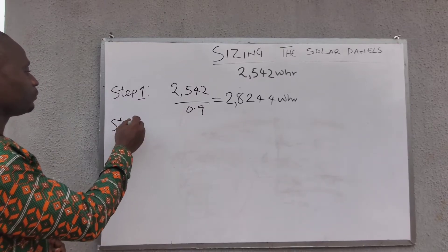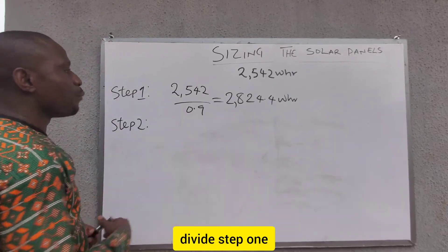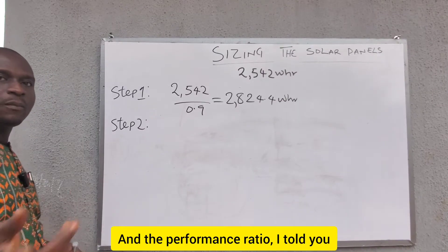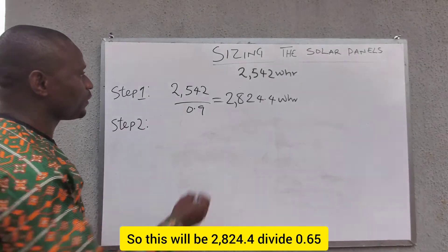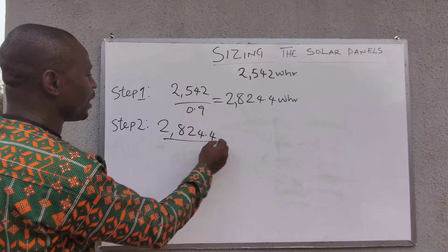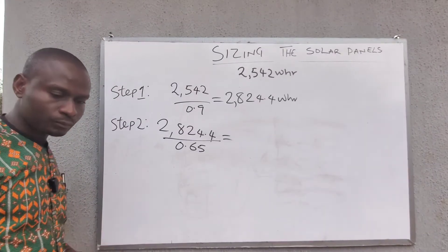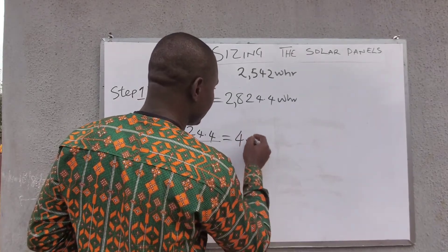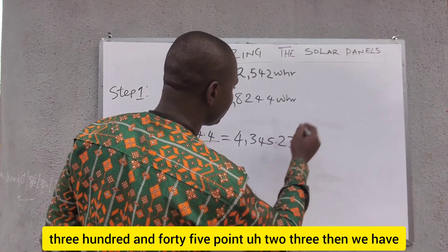Step 2: divide the result from Step 1 by the performance ratio of the panel. We are using 0.65. So 2,824.4 divided by 0.65 gives us 4,345.23.